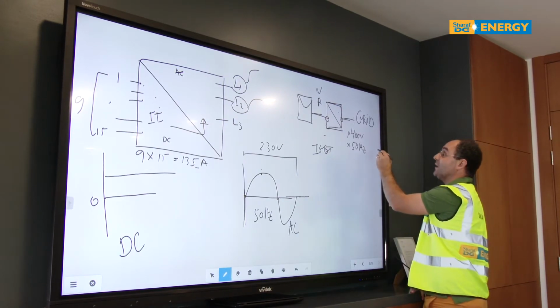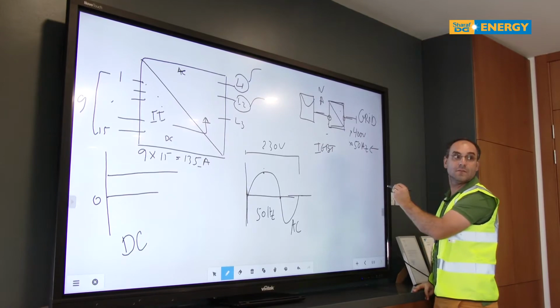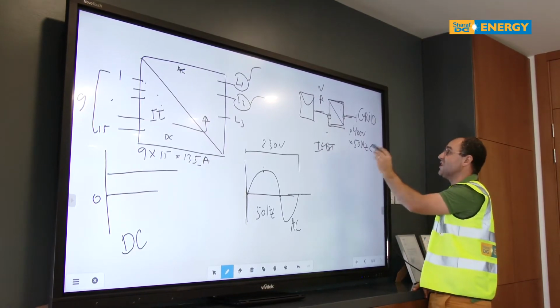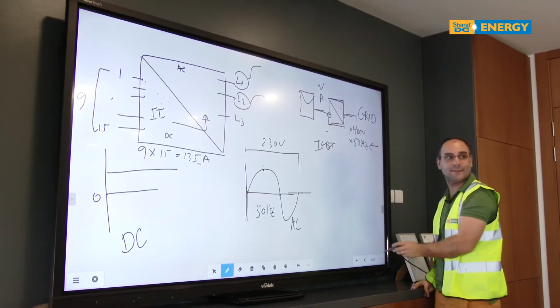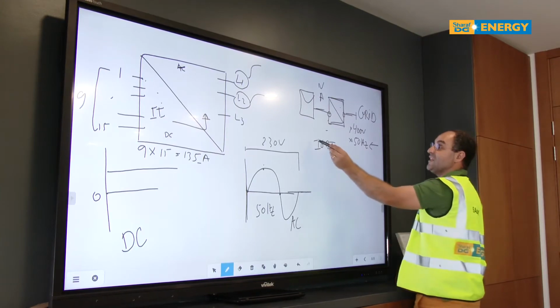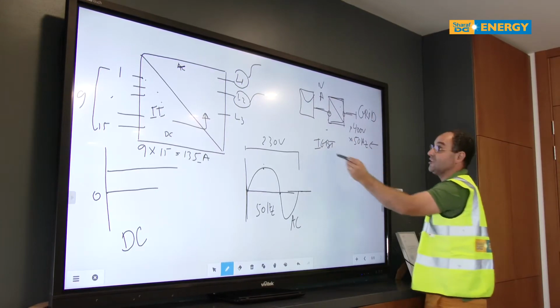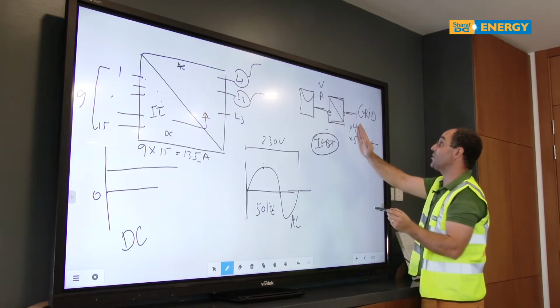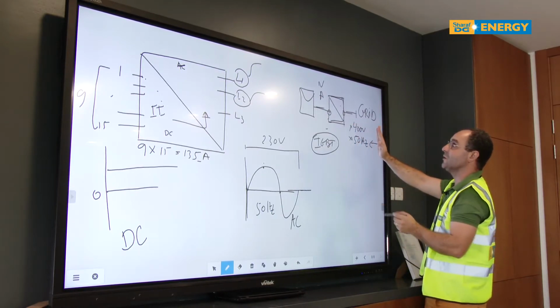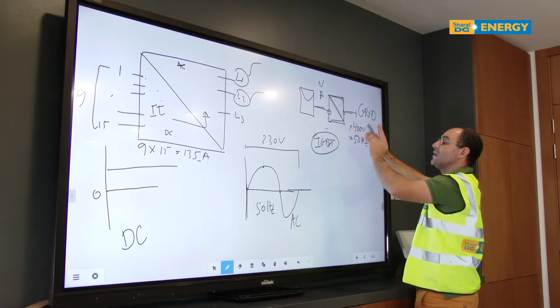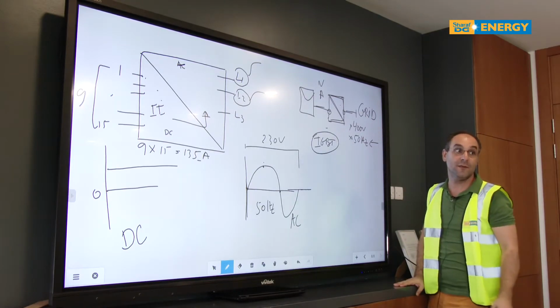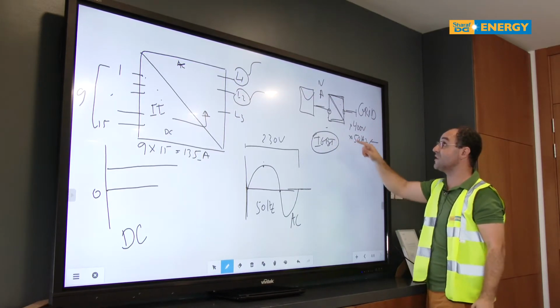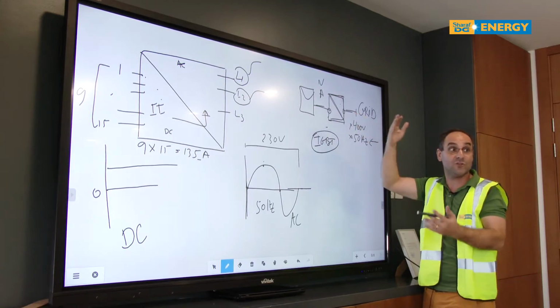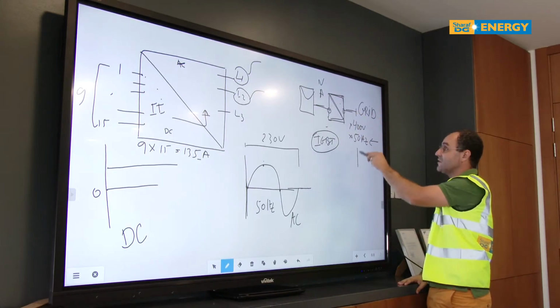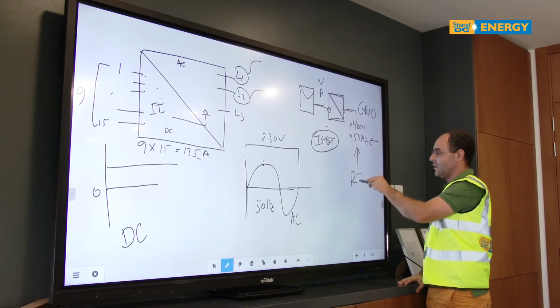So if one of these values fails, if it goes to 60 or to 100 or something, or if it goes dead, this guy will also know, I no longer have these values, so please unhook from the grid. Because if I don't know what the values are, I cannot generate anything. I don't know the reference. This is the reference.